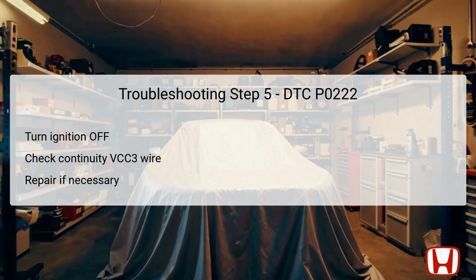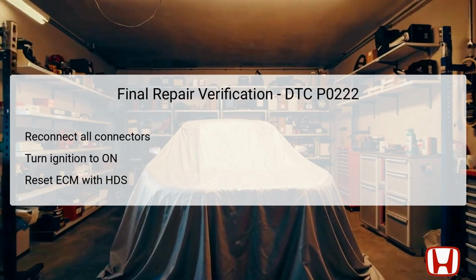If continuity is present, it indicates that the VCC3 wire is functioning correctly, and you should consider updating the ECM software or substituting it with a known good part if the system hasn't been updated recently. If there is no continuity, however, this indicates an open in the wire that must be repaired before any further actions are taken. To conduct final repair verification, ensure that all connectors are properly reconnected after repairs are made.